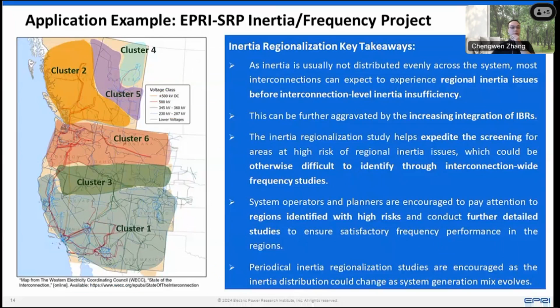So a few key takeaways for this inertial regionalization study approach. Inertia is usually not distributed evenly across the system, so most interconnections can expect to experience regional inertia issues instead of interconnection-level inertia insufficiency. This can be further aggravated with increasing integration of IBRs in a specific location.